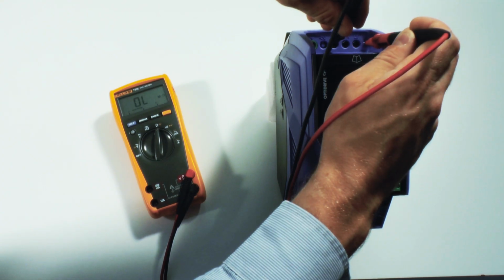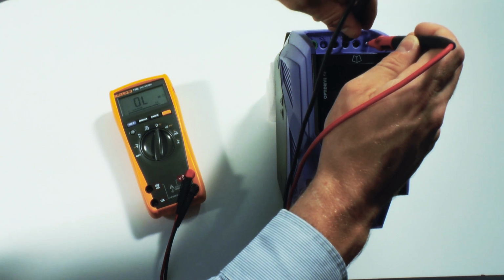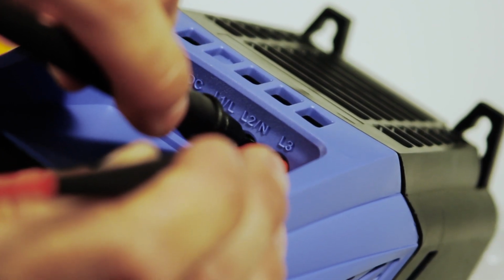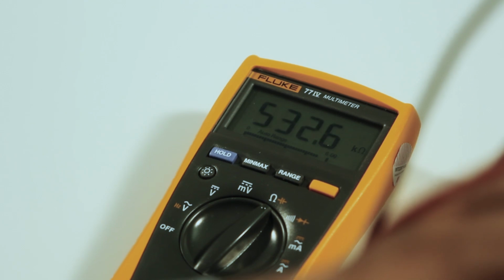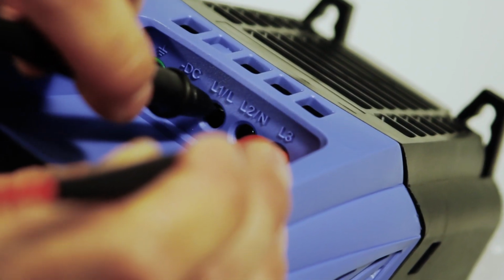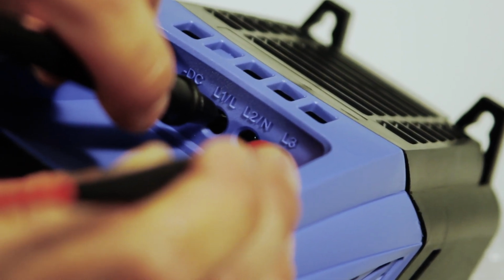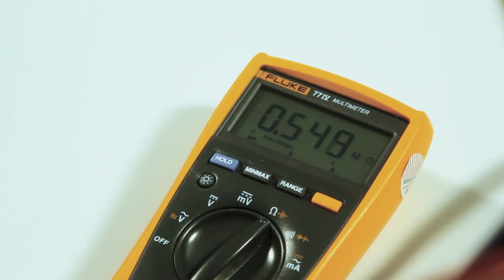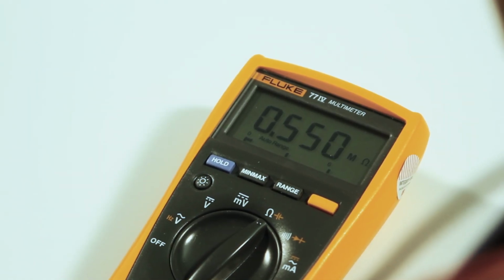Repeat the process for the following test points. Place the black lead on L2 and the red lead on L3. Then place the black lead on L1 and the red lead to L3. Complete the service request form with your readings.